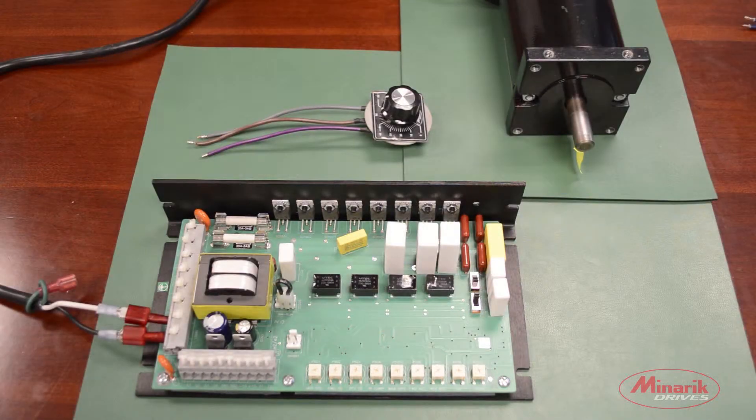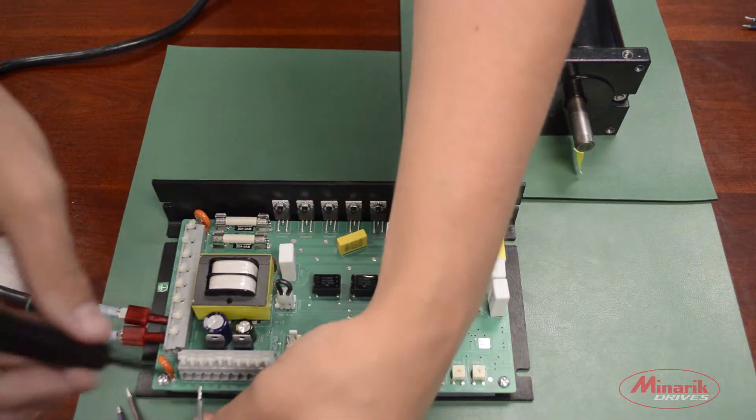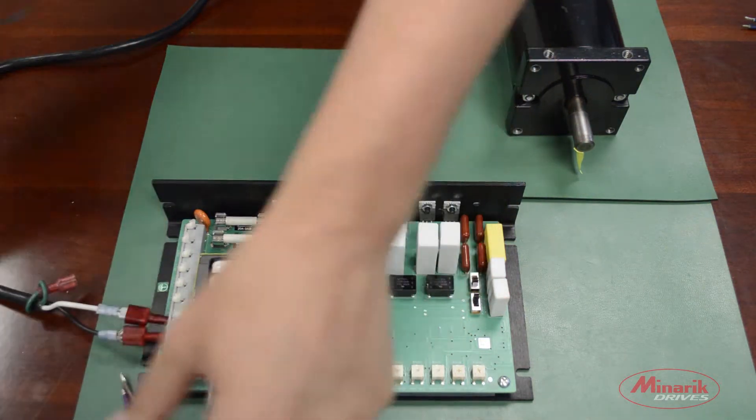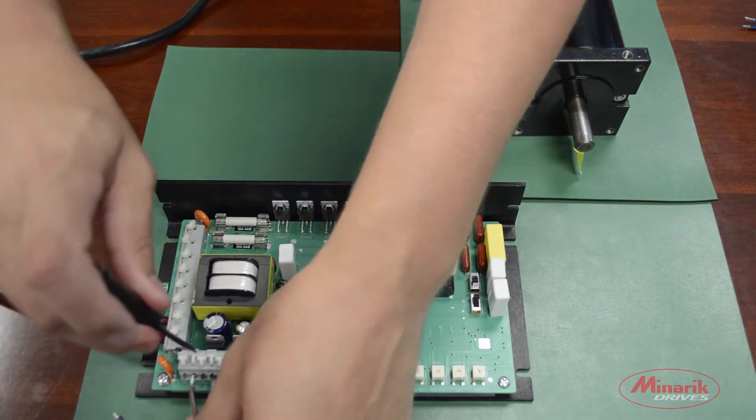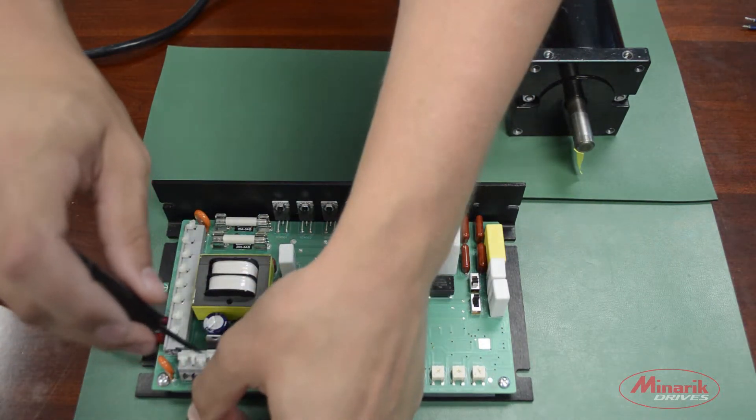Next we're going to wire up a speed potentiometer. We're going to take the common lead and wire that to S0, the wiper to S2, and the positive lead of the potentiometer to S1.